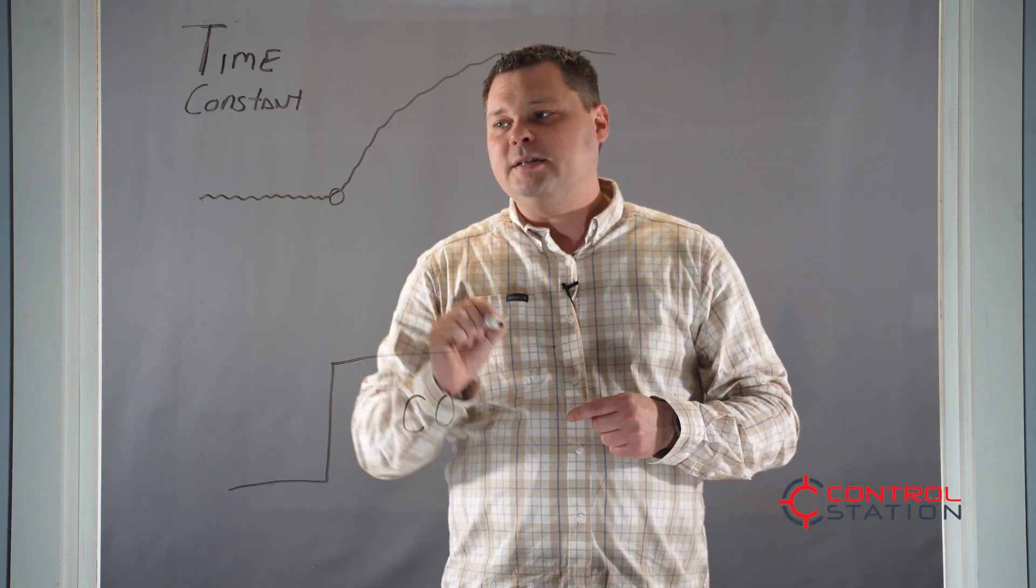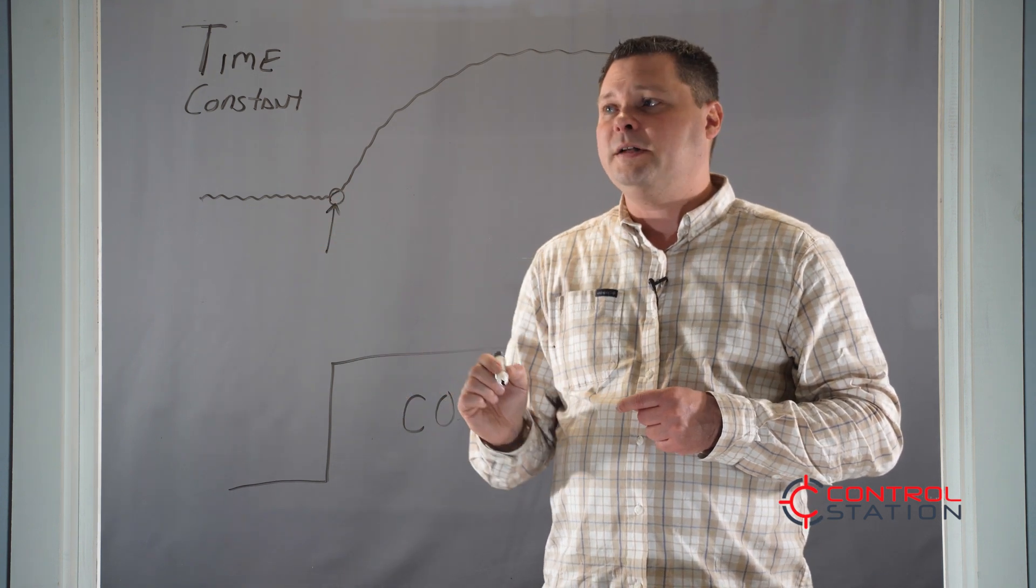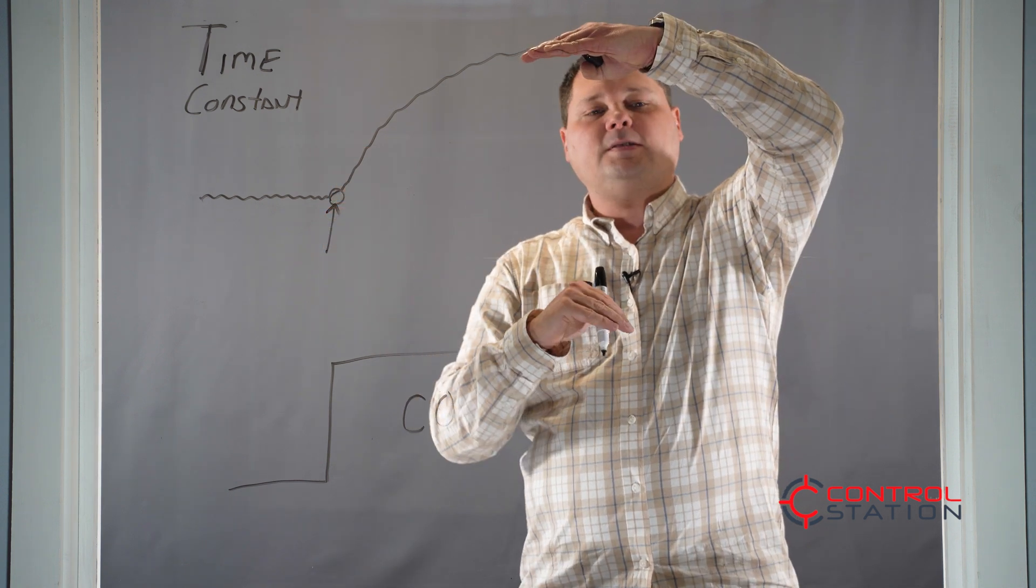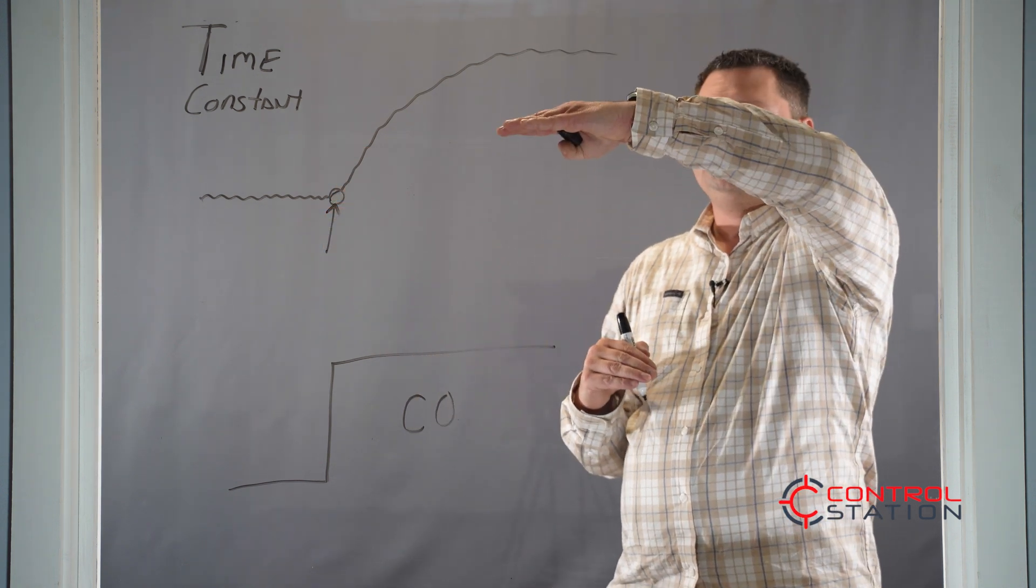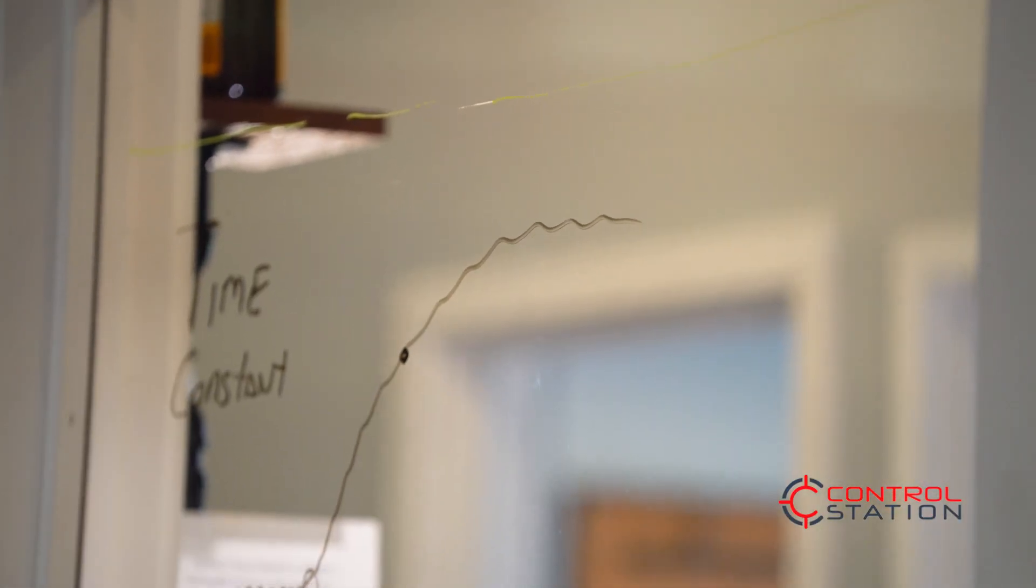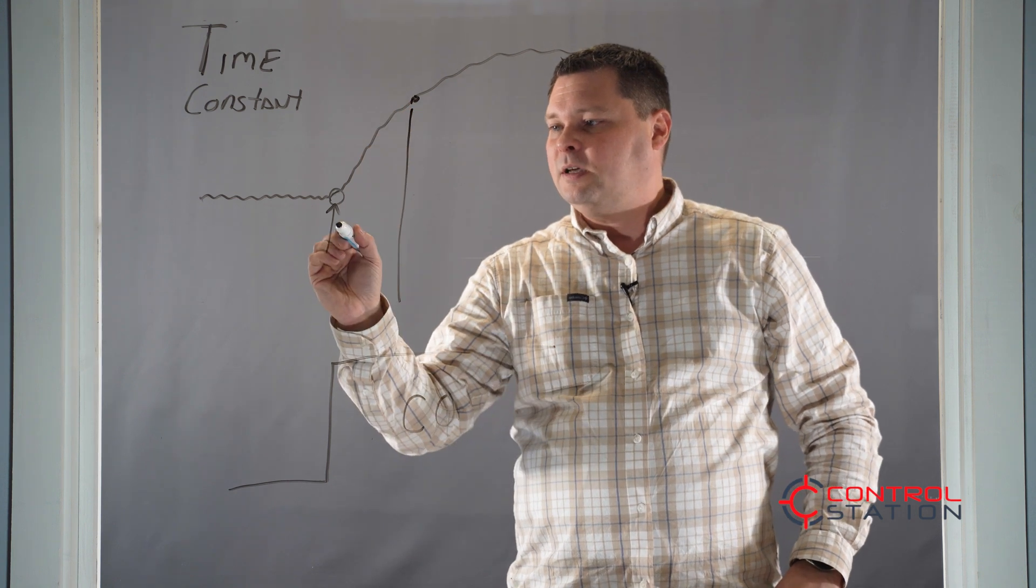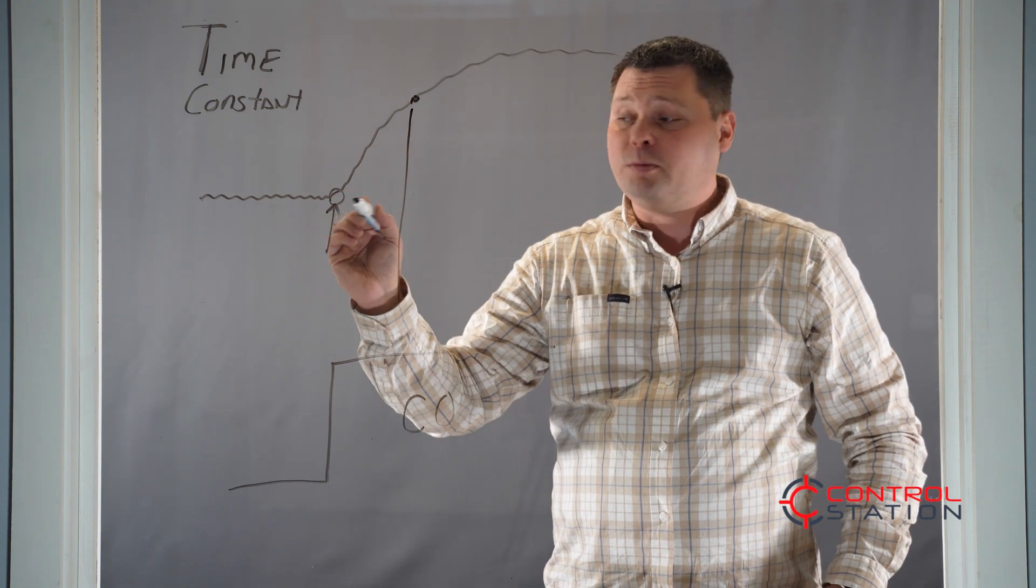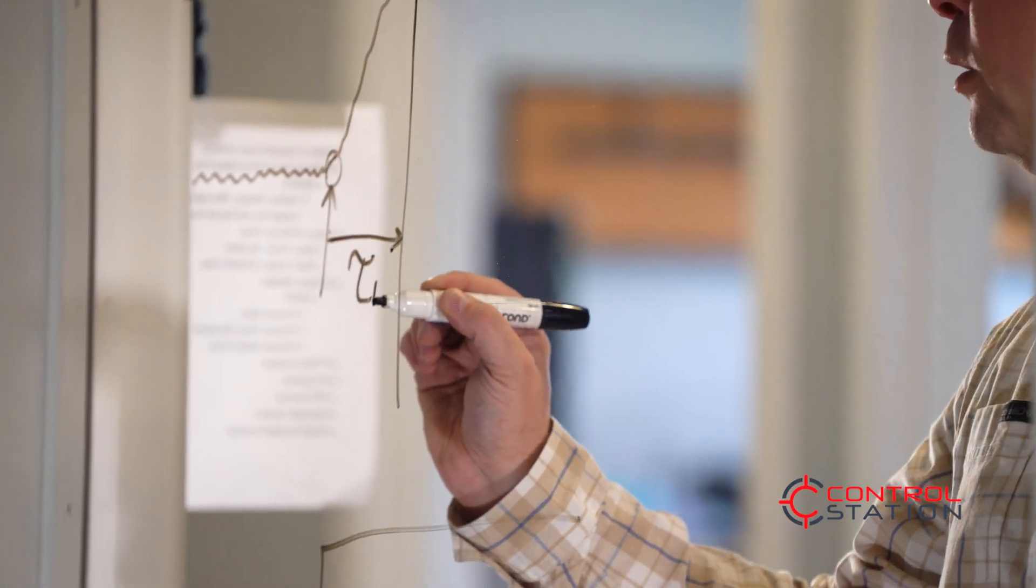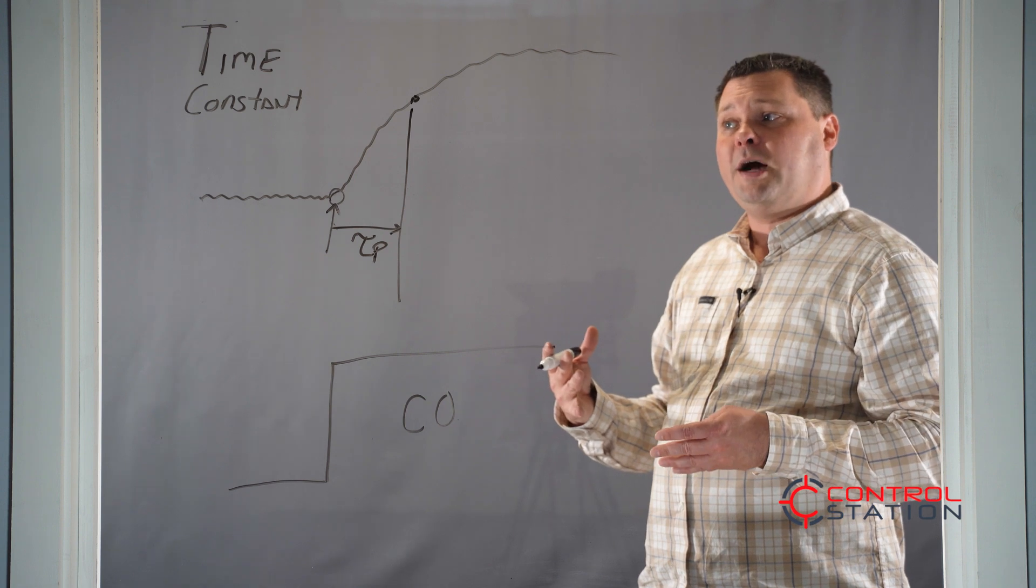Specifically, a time constant is the time it takes from when the process first starts to respond till it reaches about 63% of the way there. So if this is 100% of the way there, this is halfway there, 63 is a little more than halfway. The time it takes from where the process started to respond till it reached 63% of the way there is known as a time constant or a tau p. That is the speed of the response.